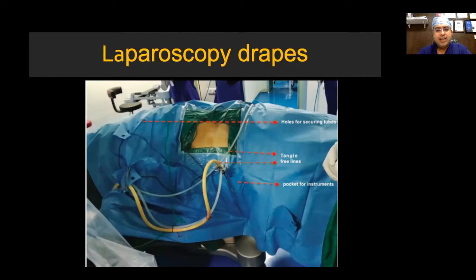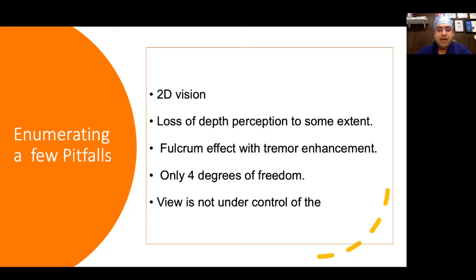You should have custom made drapes with multiple holes where instruments can be parked. An important consideration in ergonomics is that all laparoscopic instruments have only four degrees of freedom: craniocaudal, mediolateral, rotatory, and in-and-out movements. Going in and out and rotational movements are intuitive; the other two are counterintuitive. When there is a counterintuitive movement, the laparoscopic instrument moves on a fulcrum — it behaves like a lever.